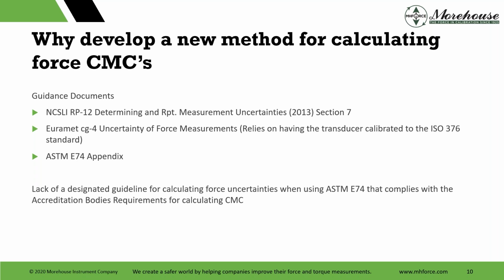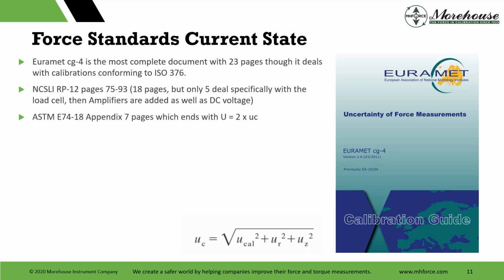And then there's just lack of, like looking at this, there's lack of designated guideline for calculating force uncertainties when using a standard such as E74 or others that accreditation bodies like PJLA and the other ones would use for calculating their calibration and measurement capability to verify you're calculating it, depending what side you're on. So Euramet CG4, in my opinion, was the most complete document. It's 23 pages total. NCSLI RP-12, there's pages 75 to 93. It's 18 pages, but only 5 specifically deal with a load cell. Then amplifiers are added as part of DC voltage. Not that many people use amplifiers. I would guess the number of people we have, maybe a couple out of the whole group of people attending. And then the ASTM appendix is 7 pages, and it basically ends with, hey, take U times all of this stuff squared, and RSS, square root of the sum of squares, all that fun stuff.